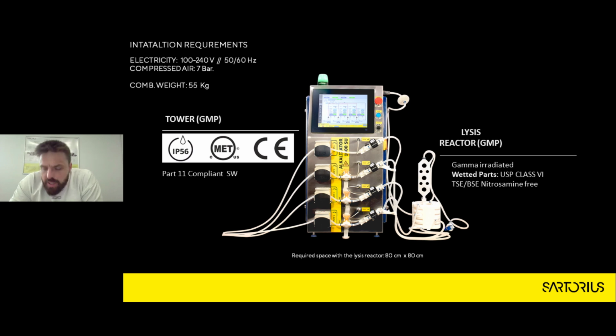This is basic laboratory compressed air, so you just plug it in from the back at a starting pressure of 7 bar, and the machine will automatically reduce those 7 bars down to 2 bars internally, and what comes out in the lysis reactor will be somewhere between 1 to 2 liters per minute.